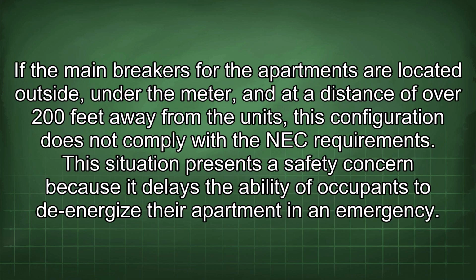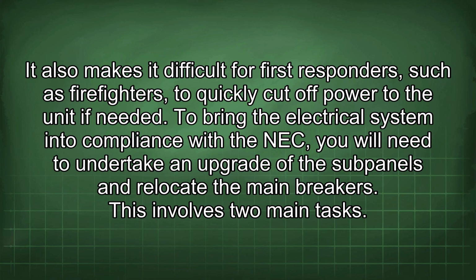If the main breakers for the apartments are located outside, under the meter, and at a distance of over 200 feet away from the units, this configuration does not comply with the NEC requirements. This situation presents a safety concern because it delays the ability of occupants to de-energize their apartment in an emergency. It also makes it difficult for first responders, such as firefighters, to quickly cut off power to the unit if needed.